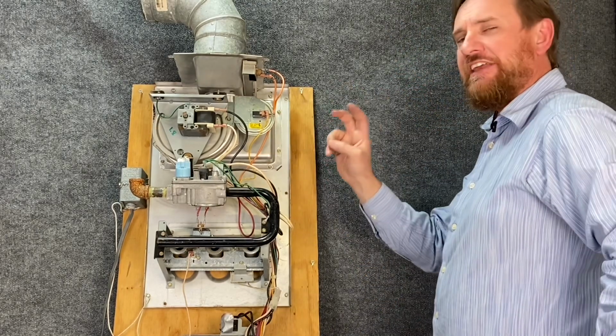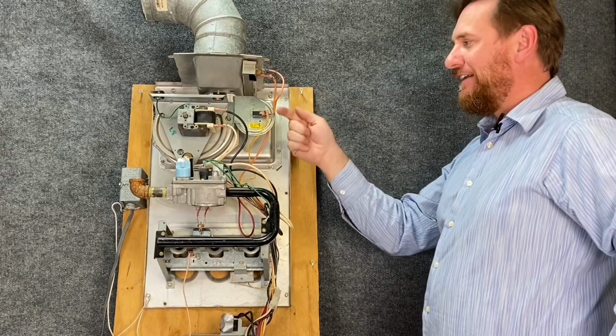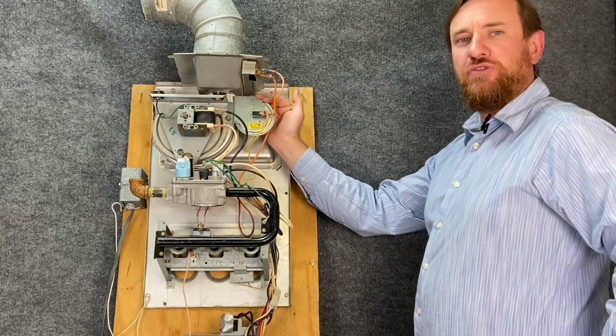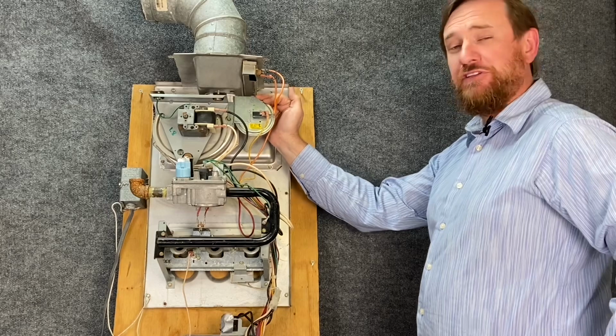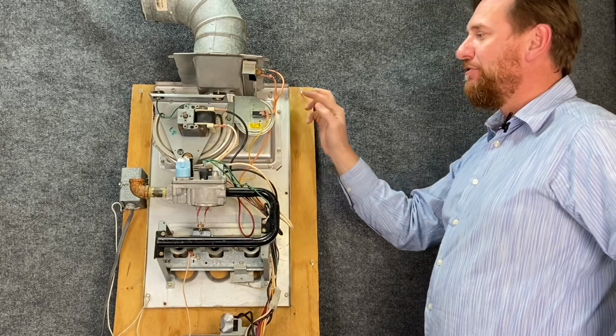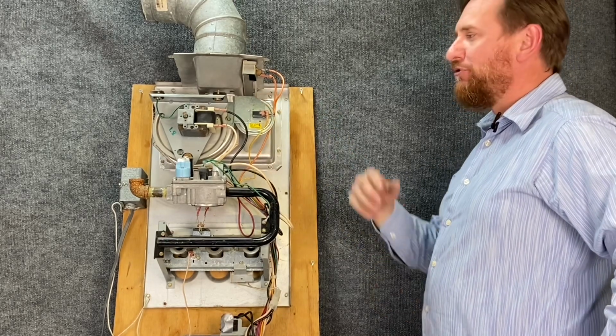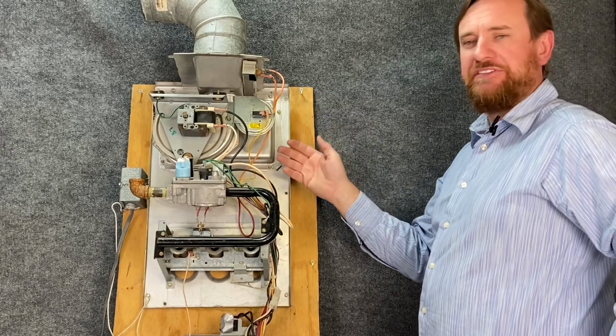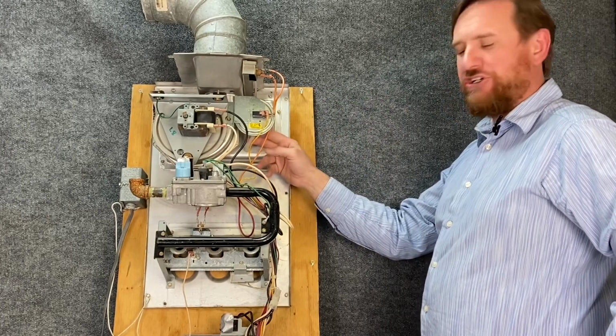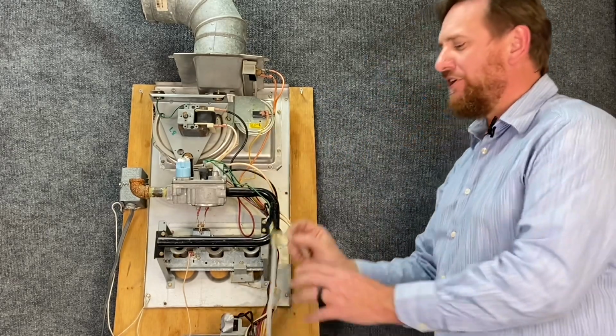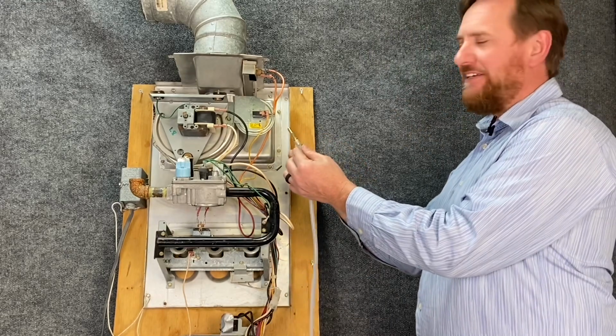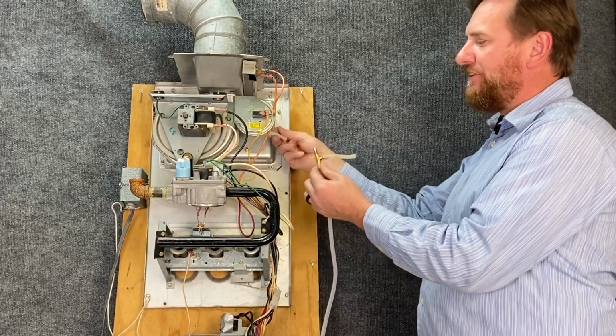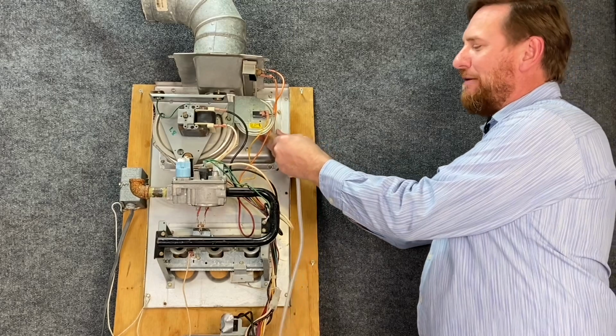This switch, we need to think about it as a pressure and a switch. So we need to make sure, do we have the proper vacuum coming to the switch first? Then if we do, let's see if the switch closes. So we're going to fire this system up and go through that process. But how are we going to check to make sure we have that happening? What we're going to use is this nice little brass tee. I'm going to unplug the existing hose, and I'm going to connect it to my brass tee.